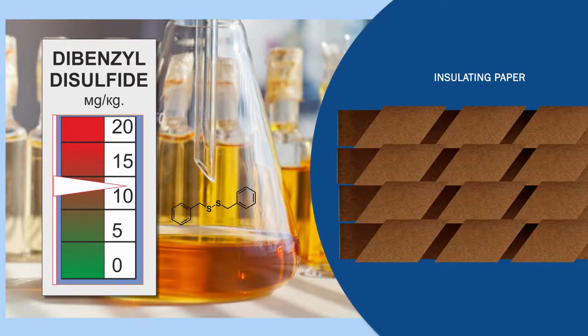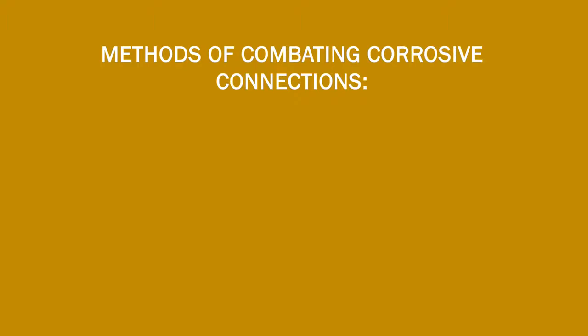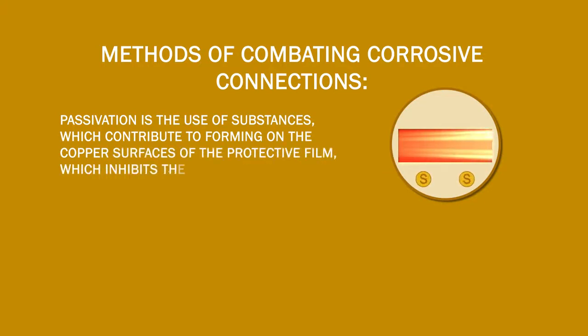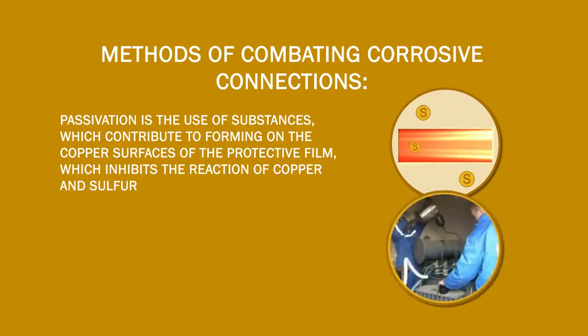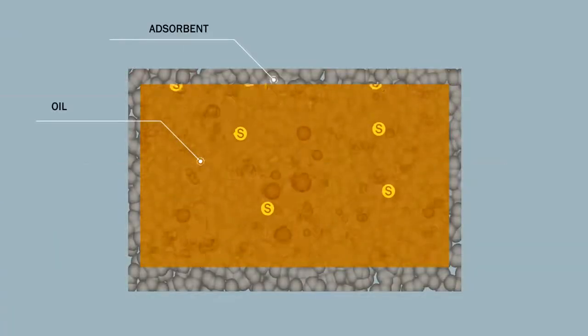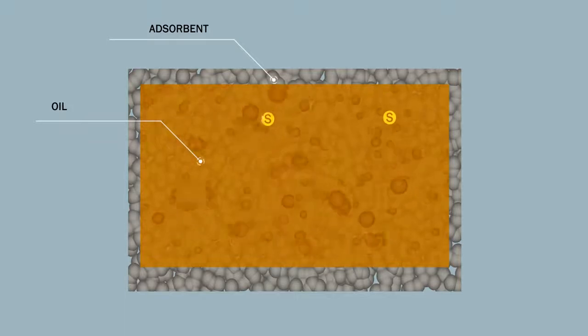There are several ways to tackle corrosive compounds, such as passivation, total oil change, or adsorbent treatment. Passivation is the process of forming a protective film on the copper surfaces using special substances to prevent the reaction between sulfur and copper, but its efficiency is limited by the wide variety of alloys and metals used as transformer construction materials. A total oil change is also not a complete solution, as even after such a change, some old oil remains in the transformer, including contaminants such as corrosive sulfur. Using one adsorbent for the whole range of corrosive sulfur compounds is also rather pointless.